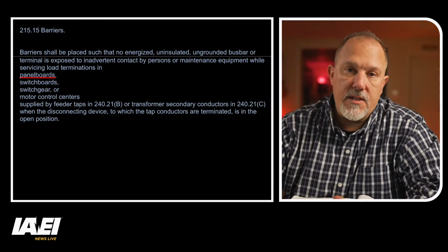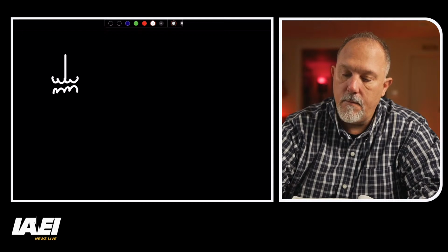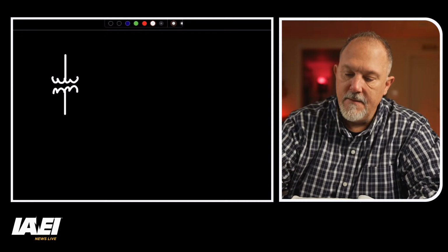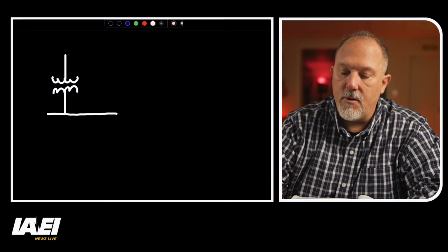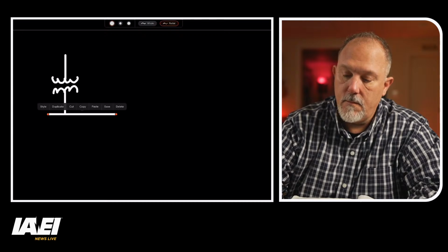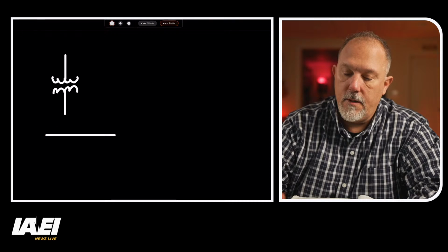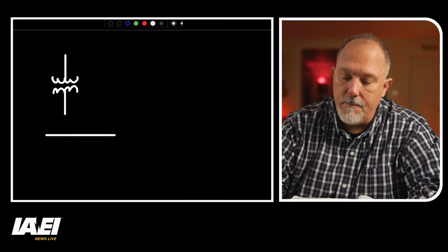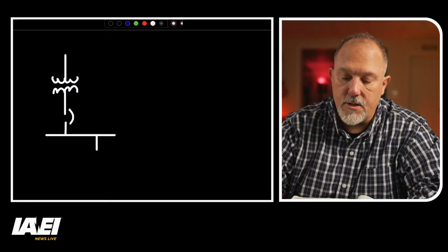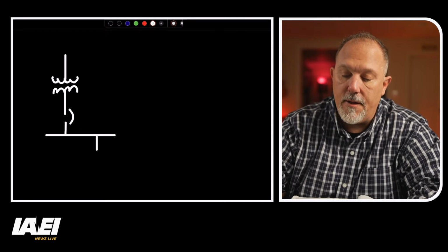Now, what this section is basically recognizing is that when I have, say, a transformer that feeds a panel board, and anytime a transformer feeds a panel board, you have to have a circuit breaker as the main in that panel board, or a circuit breaker just ahead of it. But it has to be on the load side of the transformer.